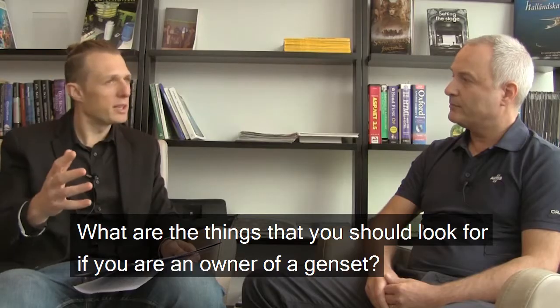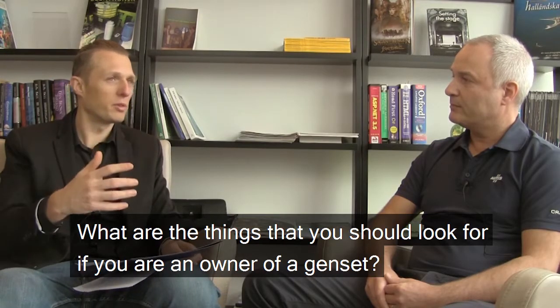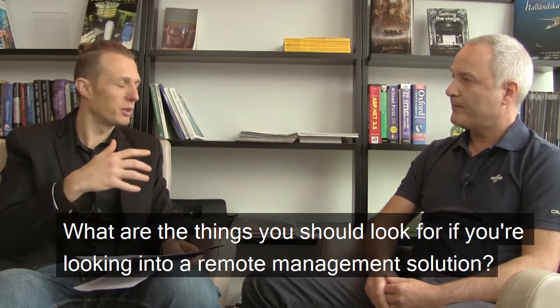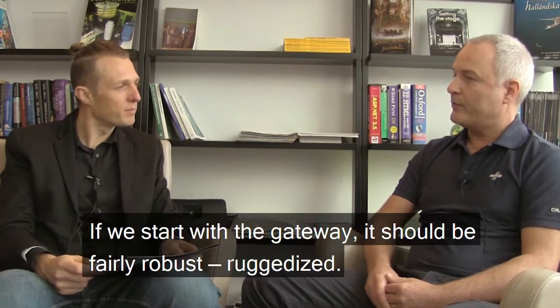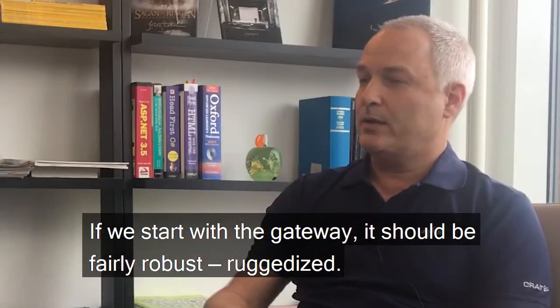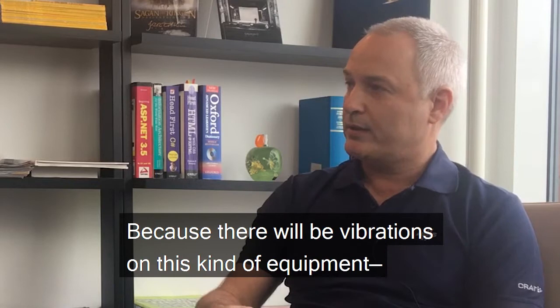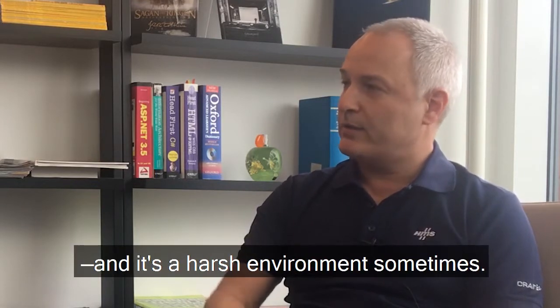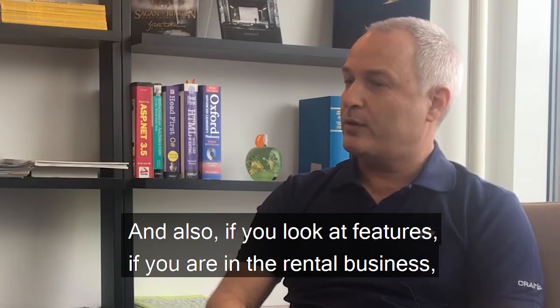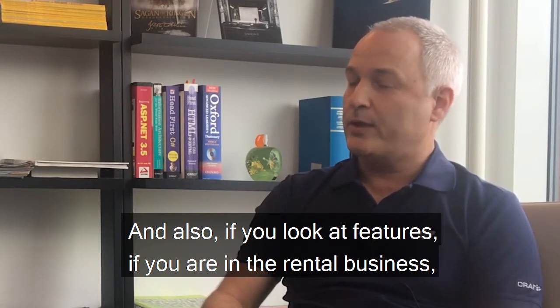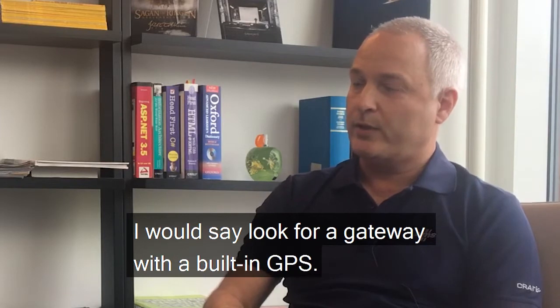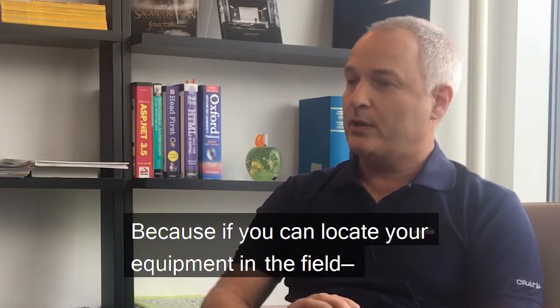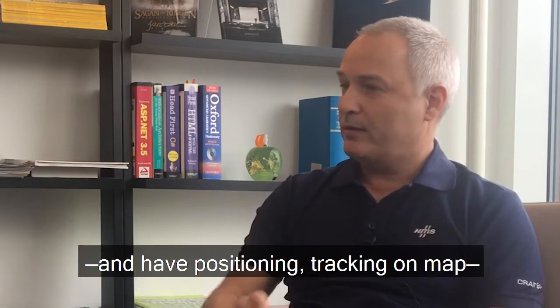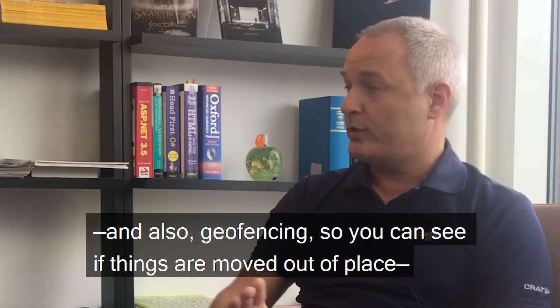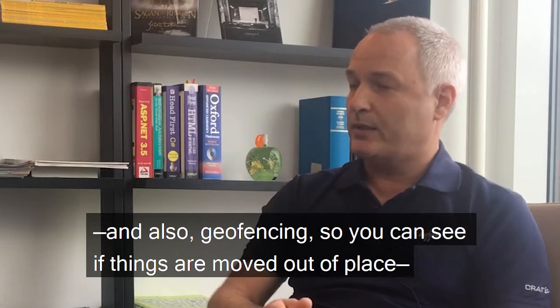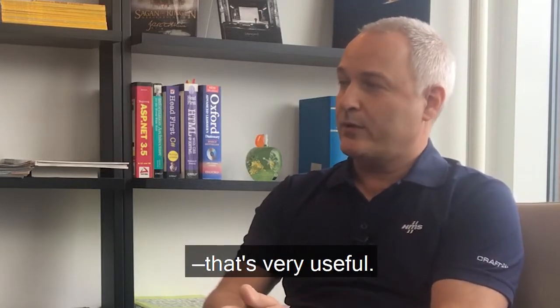What are the things you should look for if you're an owner of a genset, when looking into a remote management solution? If we start with the gateway, it should be fairly robust, ruggedized, because there will be vibrations on this kind of equipment, and it's a harsh environment sometimes. Also, if you're in the rental business, I'd say look for a gateway with built-in GPS, because if you can locate your equipment in the field, have positioning, tracking on map, also geofencing so you can see if things are moved out of place - that's very useful.